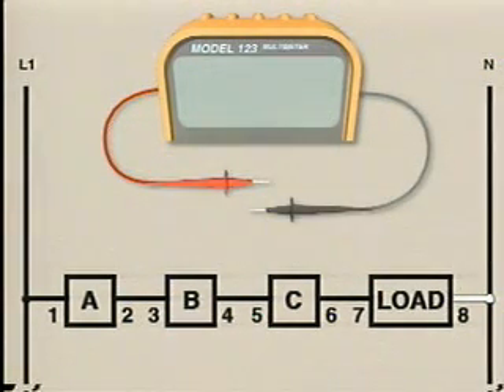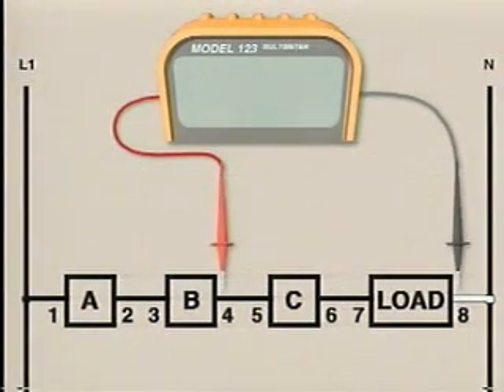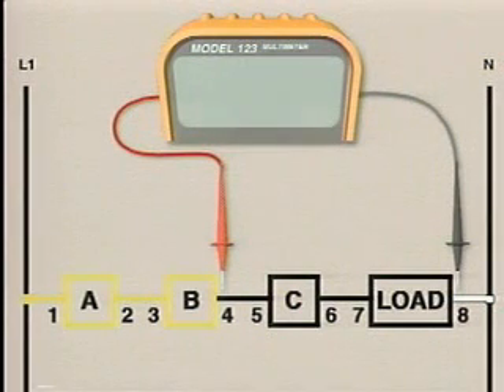So now we're ready to start checking the circuit's components. To begin half-splitting, we need to split the circuit in half. The wire that connects control device B to control device C is in the middle of the circuit. This means that either test point 4 or test point 5 can be used to half split the circuit. We'll use test point 4. This test will check all of the components from L1 to test point 4.